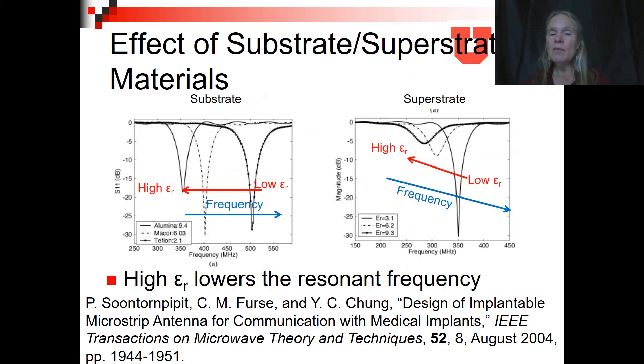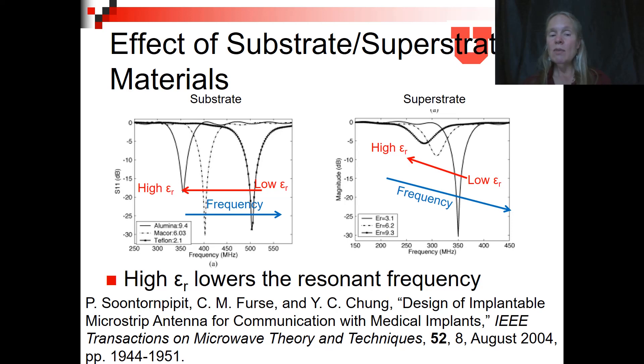We considered different materials for the substrate and superstrate. Using a high dielectric material lowers the resonant frequency — effectively making the antenna electrically larger — while a low dielectric raises the frequency, making the antenna electrically smaller. The difficulty at this time was that there were not very many high dielectric materials that were also biocompatible. The three we chose were Teflon, Macor, and Alumina, with dielectric constants ranging from 2 to almost 10.